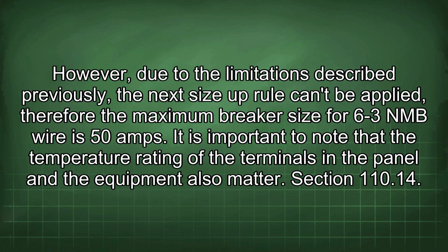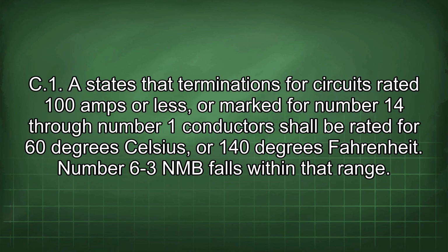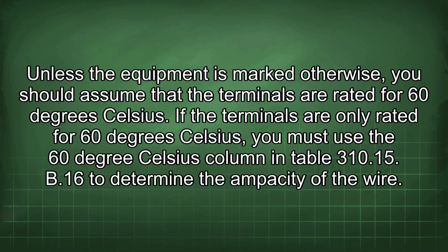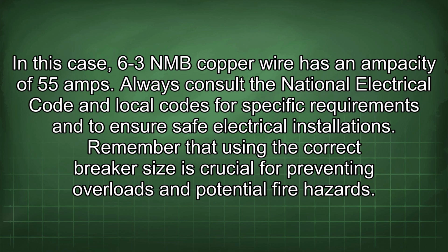It is important to note that the temperature rating of the terminals in the panel and the equipment also matter. Section 110.14(C)(1) states that terminations for circuits rated 100 amps or less, marked for number 14 through number 1 conductors, shall be rated for 60 degrees Celsius or 140 degrees Fahrenheit. Number 6-3 NMB falls within that range. Unless the equipment is marked otherwise, you should assume that the terminals are rated for 60 degrees Celsius. If the terminals are only rated for 60 degrees Celsius, you must use the 60 degrees Celsius column in Table 310.15(B)(16) to determine the ampacity of the wire. In this case, 6-3 NMB copper wire has an ampacity of 55 amps.